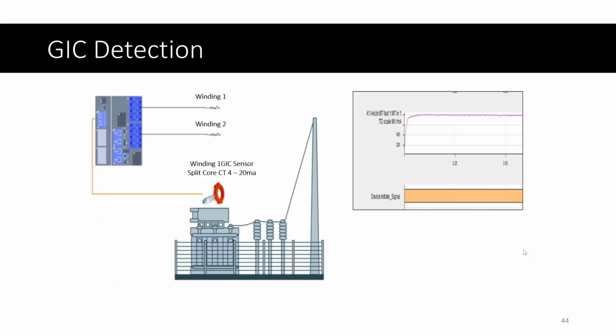Next slide, please. And then the GIC detection is using a split core 4 to 20 milliamp sensor on the neutral of the auto transformers. That allows us to capture the quasi DC in real time, and then we can alarm off of that. It could be programmed to also take control actions such as opening circuit breakers to isolate transformers, but our intent right now is just to use it in a monitoring mode. Next slide, please.